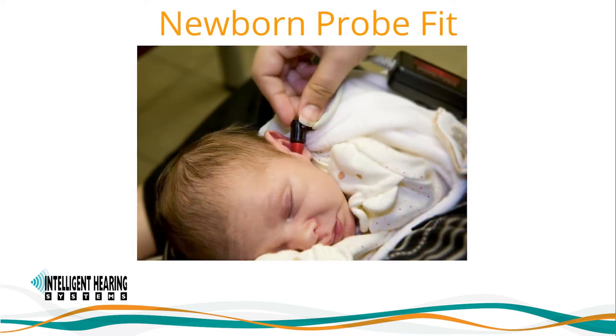Let's discuss the details of a good newborn probe fit. Newborn ear canals tend to be sticky. To address this, clinicians can massage the area in front of the ear in a circular motion for 10 to 15 seconds. Then gently pull out on the pinna or outer ear and rotate in a circular motion for a few seconds to unstick the ear canal before inserting the probe. When inserting the probe into the baby's ear, pull back and down on the pinna to fully open the ear canal and help obtain a good probe fit. Release the pinna after insertion, letting the ear canal fall snugly around the probe.